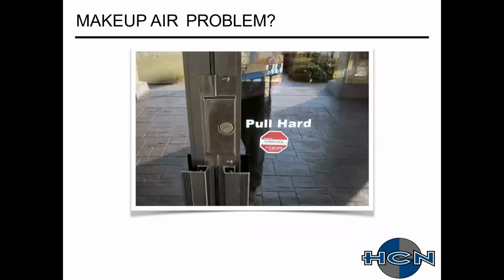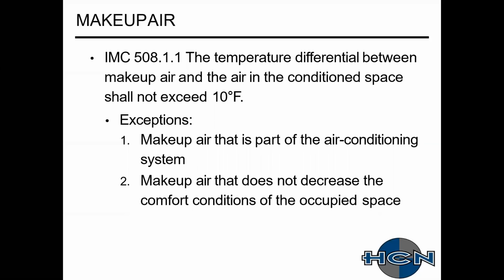Next thing we're going to talk about is makeup air, optimizing the way it's delivered into the kitchen and the hood environment. I'm sure people have seen signs like this, pull hard. Even then, in some places you go in, you can feel the difference, especially in the winter months. When you go into a pizza place or something right now, you can pull on that door and it's pretty hard to open because they turn off their makeup air, typically, and they have a negative balance in that space. IMC 508.1 requires that you bring in that makeup air within 10 degrees of the space. There are some exceptions, such as makeup air that's part of the air conditioning system and doesn't decrease comfort conditions. The big thing I would say is we really don't want to be designing for the exceptions for the makeup air.